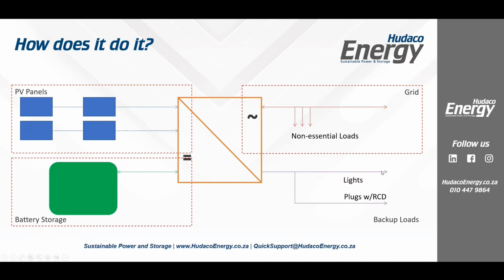Okay, very important. This is not bidirectional. This is one way only. These loads are the loads that you will only run when grid fails. In other words, if I'm running my batteries and I have load shedding and my grid fails, I only want these loads to be able to be run by battery. Of course, if there's PV, they can run those too. That's just an extra bonus. But during a case of load shedding, my geyser can go off, my pool pumps can go off, my ovens can go off, all the rest of it can go off. All of these loads will be carried on my battery. So it's one direction only.